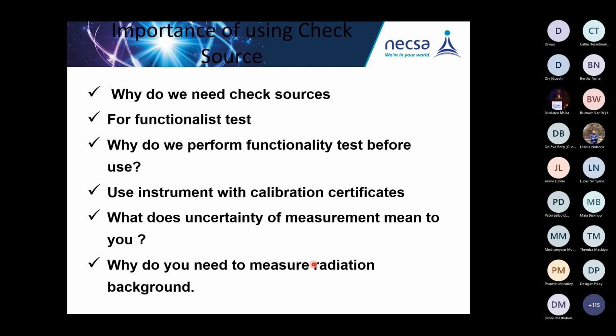And then the importance of using the check source. Why do we need to check the instrument? Also to make sure that my instrument is still measuring the same. For the functionality test, why do we perform the functionality test before use? The instrument has not been used for quite some time, but sometimes when you switch it on, it can give you readings. But for you to be sure of those readings, you need to test them against your check source. Use the instrument with the calibration certificate. Never swap the probe or swap anything, like what I've said before.